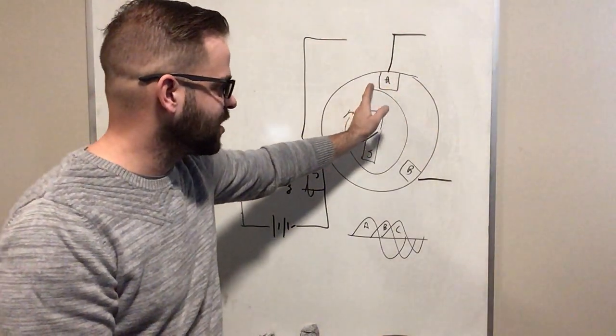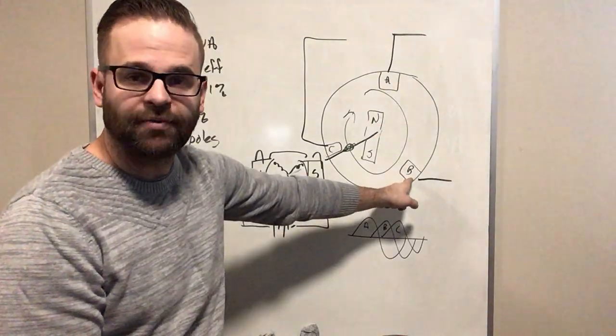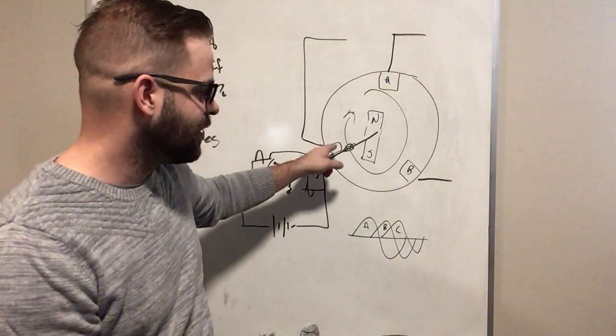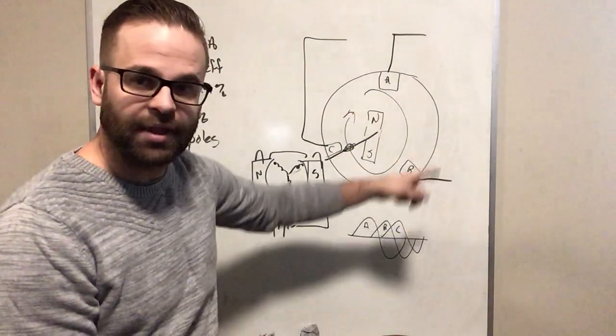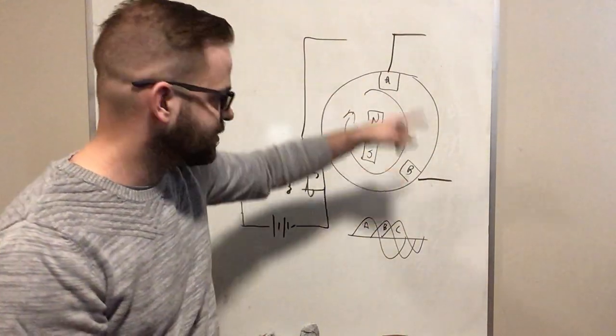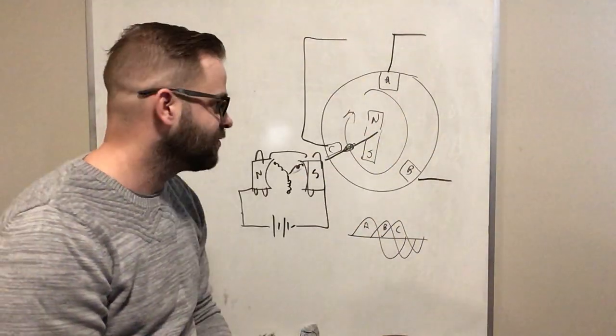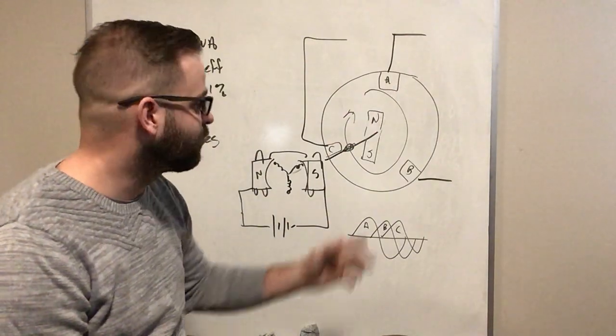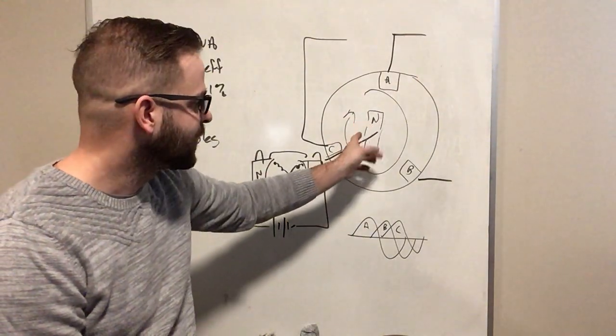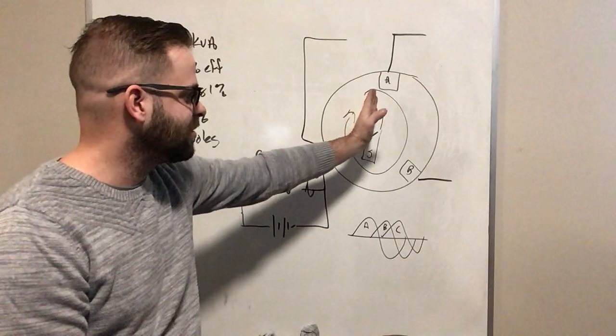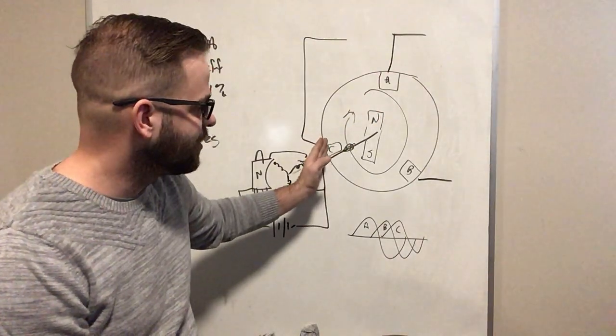Before it's even got a chance to start moving, my magnetic field would be here, then it'd be here, then it'd be here. Remember, in the lab, a rotating magnetic field is turning at 1800 RPM. So before that shaft could even get up and going, the magnetic field would now be here and it'd be trying to pull that shaft back the other way. And when it went to pull back the other way, then my magnet's here.